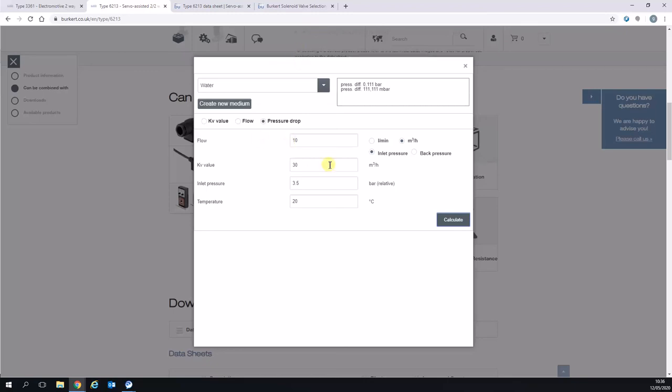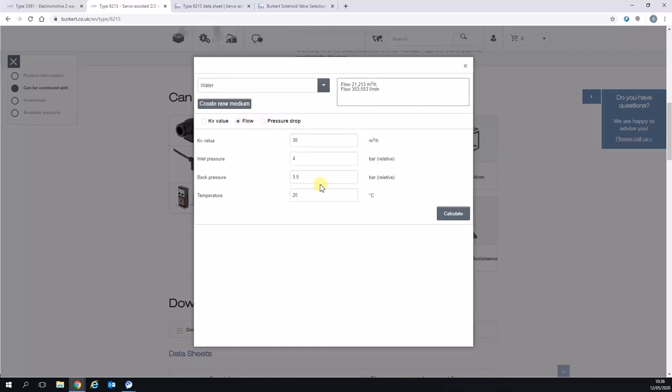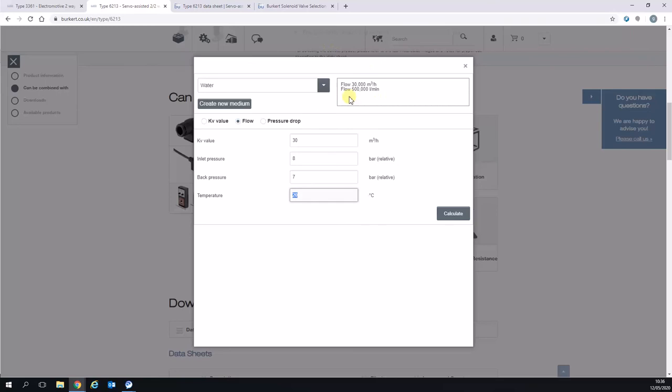The other thing we can also use this for is to calculate whether we can achieve a flow. If we click on flow now and say we've got our two inch one again here, we've got 30 meter cube and we'll put in eight bar in, seven bar out. We can see that we can achieve 30 meters cubed per hour with that particular KV. But if we only had half a bar pressure drop, you can see that with a KV value of 30, we can only achieve 21 meters cubed per hour of flow through that valve.